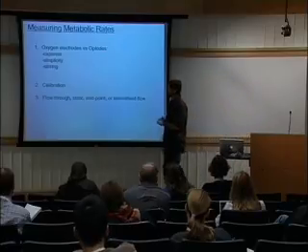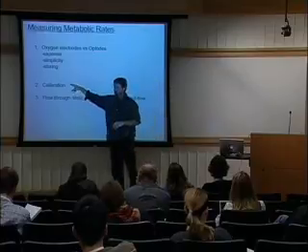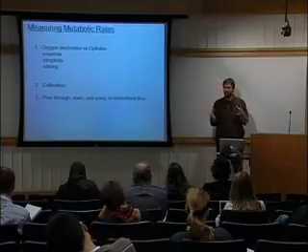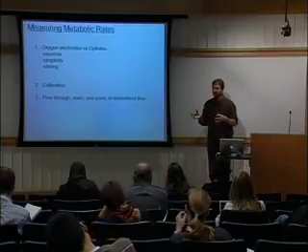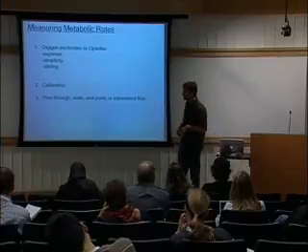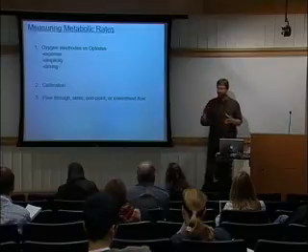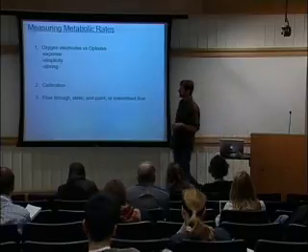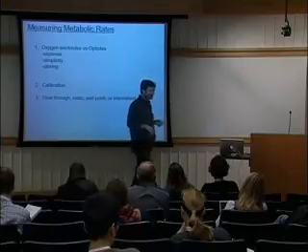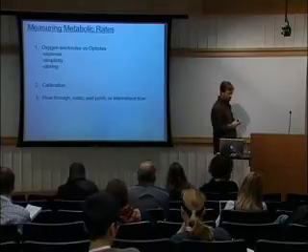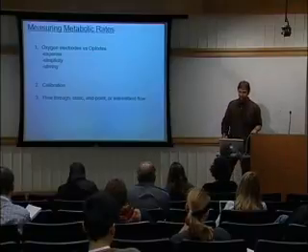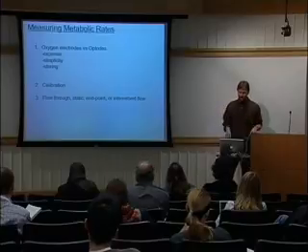Calibration is an issue. You have to know what saturation is. So you can bubble seawater with oxygen, but then there's some concern that you're oversaturating, and you have to control the temperature of the air coming in so that you don't heat up the water. So usually just some gentle stirring and being patient will get you to an air saturation level. And at the other end of the spectrum, you can bubble with nitrogen and drive all the oxygen off, which works, but it also requires patience and setup to control so that you're not allowing any oxygen to get in.